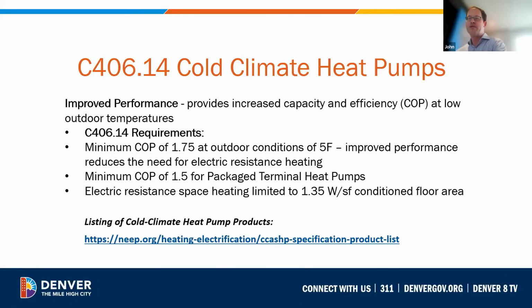Cold climate heat pumps is a new energy credit specific to Denver. These are systems that work especially well at low ambient conditions and provide much better energy performance through reduction in electric resistance heating during cold outside conditions. To achieve this credit, they have to have a minimum COP, or coefficient of performance, of 1.75 or higher at 5 degrees dry bulb ambient condition. PTACs or PTHPs, packaged terminal heat pumps, have to have a COP of 1.5.